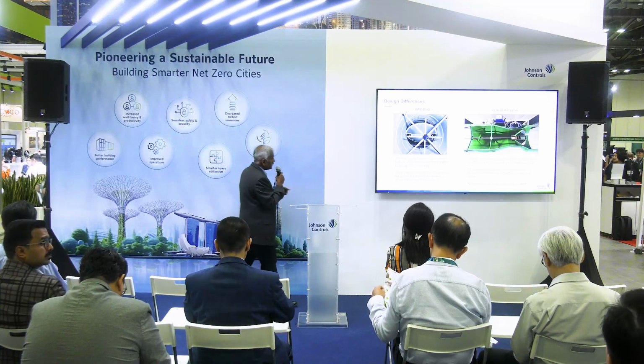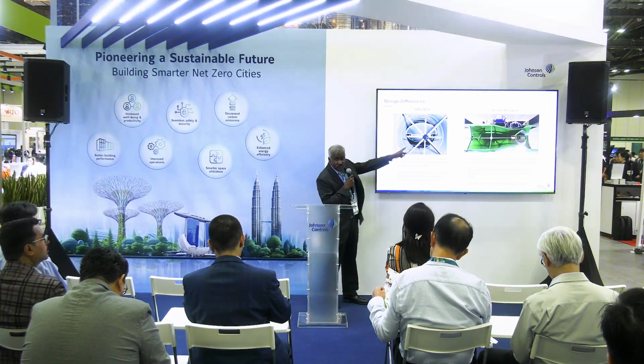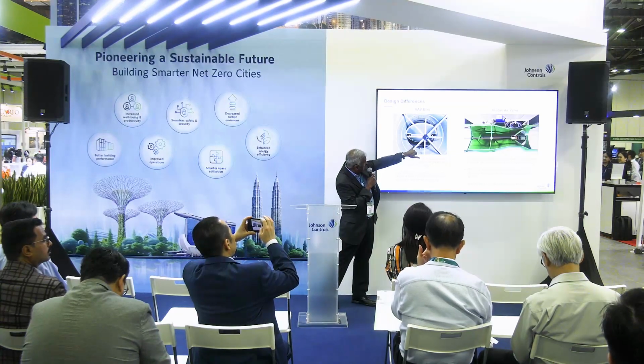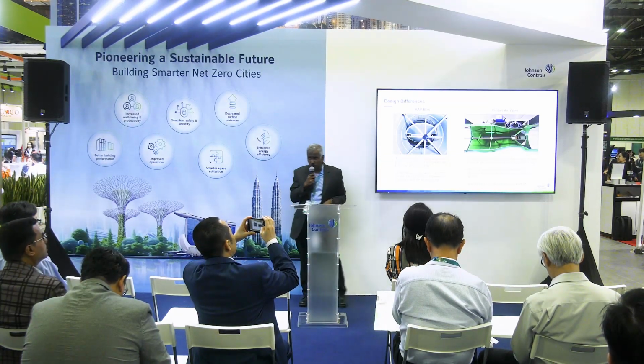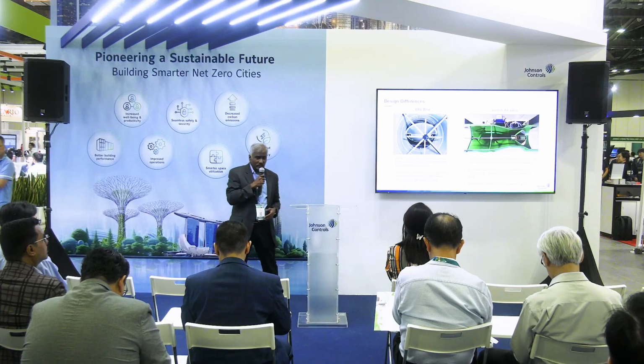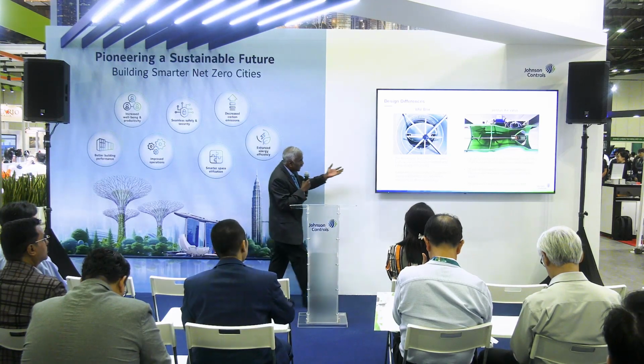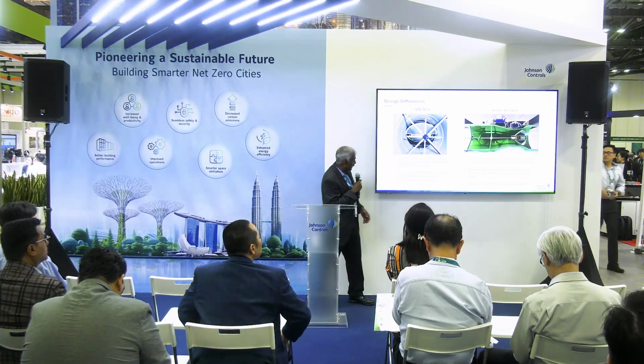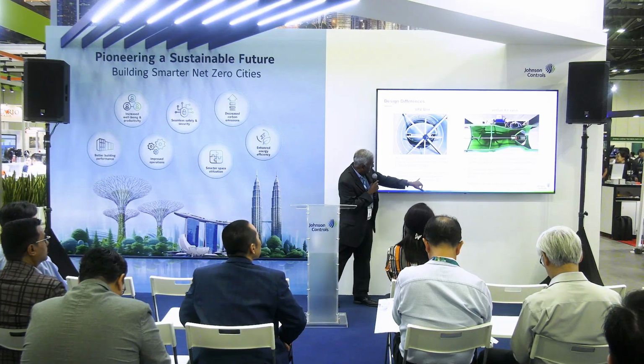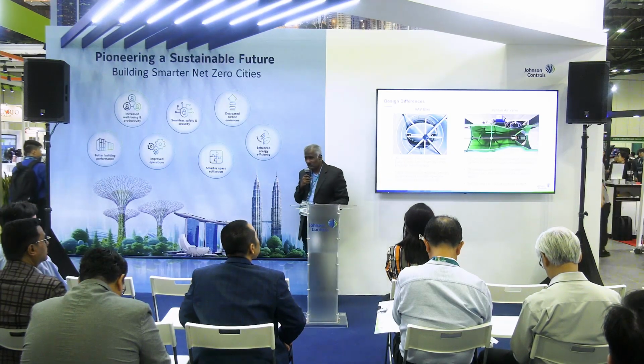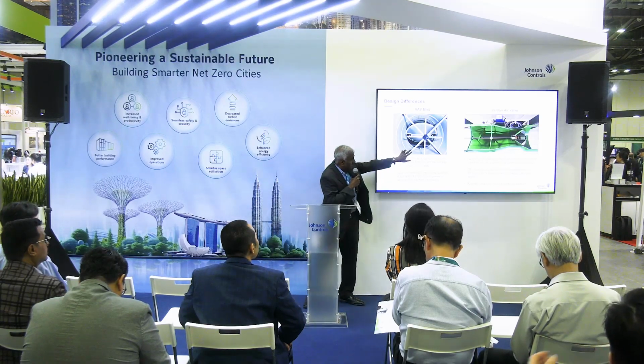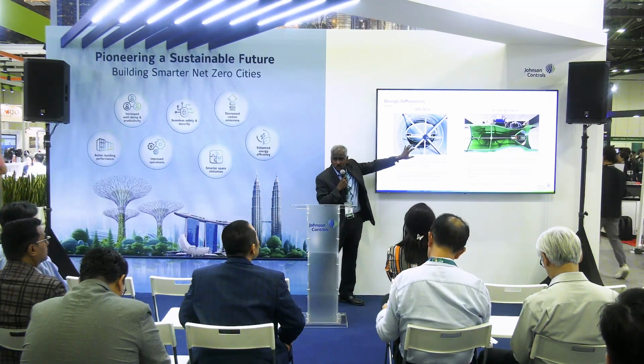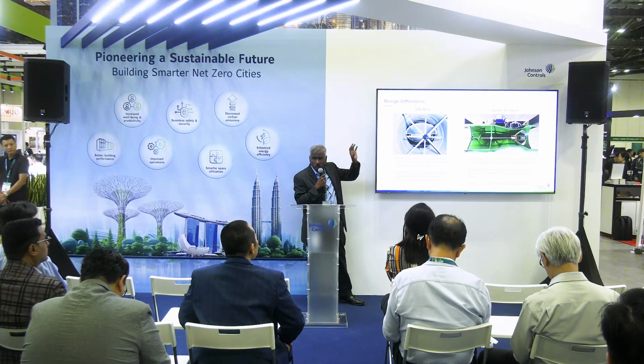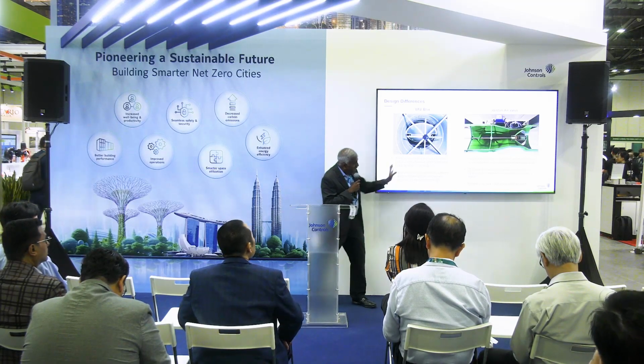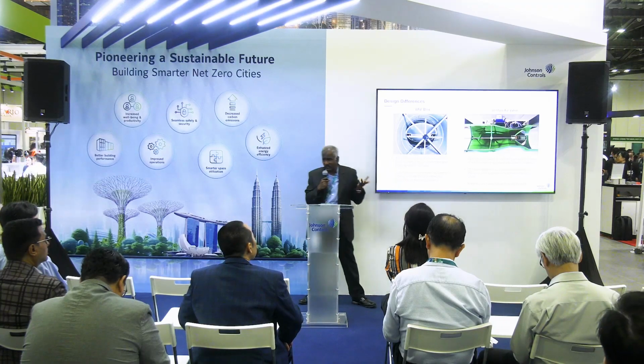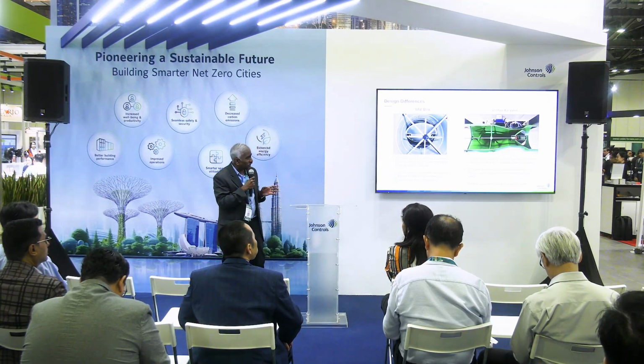Then coming back to the design difference, as I was saying, look at the flow. This is the VAV box, and you can see this is the airflow. It takes in the differential pressure, changes the velocity, and you have the CFM. So that's why it needs regular cleaning. When the sensor is blocked, the controls will open the damper to compensate and increase the flow. That's quite fundamental, because once it's blocked, it thinks there's not enough airflow. So the supply opens, the exhaust opens, and more air will come in. So you don't have the right control at all. That's one of the biggest challenges that we have.